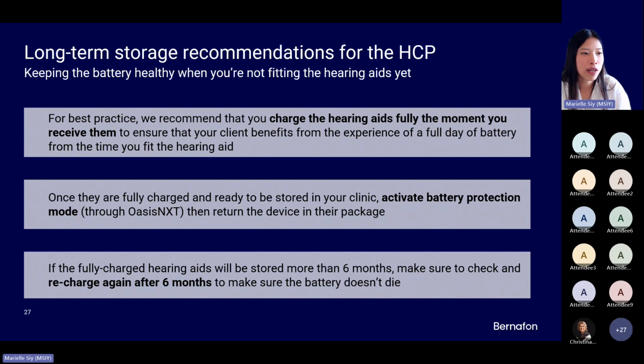Otherwise, let's look at the next ones. For best practice, we recommend that you charge the hearing aids fully the moment you receive them to ensure that your client actually benefits from the experience of a full day of battery from the time that you fit the hearing aid. Once they are fully charged and ready to be stored in your clinic, make sure to activate the battery protection mode through the OasisNXT software. Then you can return the device back to its package. Of course, you don't have to activate the battery protection mode all the time, but if you don't really expect to use the rechargeable device for more than 2 weeks, then generally we really recommend that you put it into battery protection mode to protect the battery. And I can imagine that with so many rechargeable hearing aids in your clinic, it's really hard to keep track. So it's better to do it just in case.